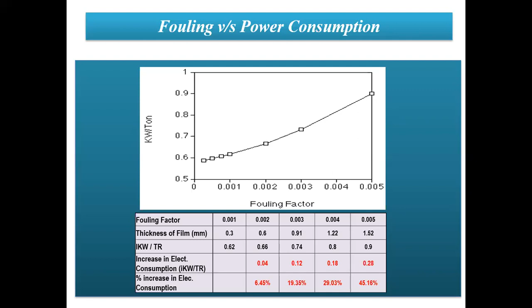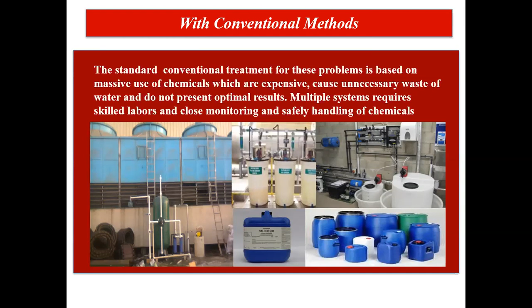Now the question arises, what's the solution to solve these problems while also maintaining the equipment and design efficiency? Those are very common pictures which we generally see at sites. Those are conventional methods, which include treatment through chemicals. It will have some barrels of chemicals, and generally three major containers: one for anti-scalant, one for biocide, one for anti-corrosive agent, then other chemicals also, some pH regulators, some passivators. First of all, this is a massive use of chemicals, which are obviously expensive, and they also need close monitoring, and the safety of handling the chemicals is another issue. Obviously, you should store the chemicals properly in a storeroom at the site.